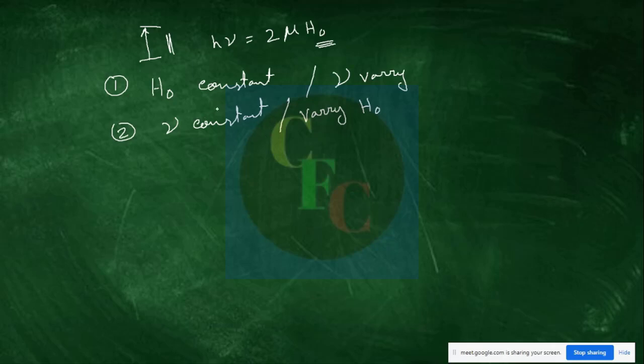Now herein the engineering thing comes in. It has been found that it is very difficult to maintain a constant magnetic field. Another important thing is that the magnetic field has to be homogeneous. Why homogeneous? Because if you have a sample here, and the magnetic field is H1 here and H2 here, they will have different energy splitting, and as such they will resonate at different frequencies.